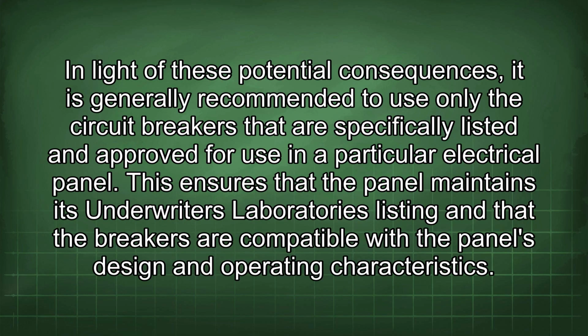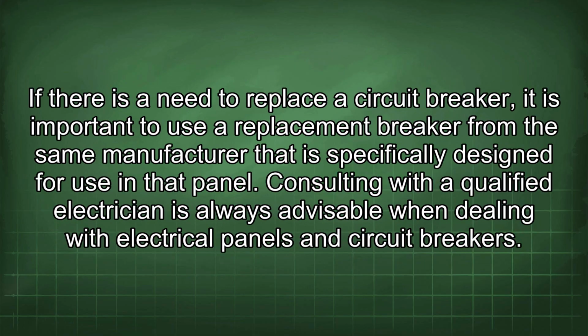In light of these potential consequences, it is generally recommended to use only circuit breakers that are specifically listed and approved for use in a particular electrical panel. This ensures that the panel maintains its underwriter's laboratory listing and that the breakers are compatible with the panel's design and operating characteristics. If there is a need to replace a circuit breaker, it is important to use a replacement breaker from the same manufacturer that is specifically designed for use in that panel.